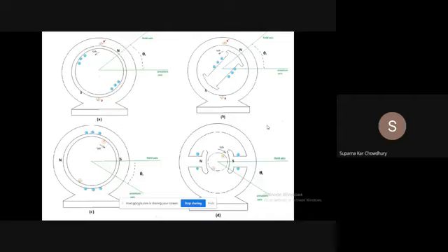So if we put our armature on the rotor, this will automatically put some limitation on the voltage rating of the armature coil. From the current rating point of view, as the current rating increases, the copper content of the winding will increase, because we will have thicker copper sections. That will make the weight of the winding bulky, and so the rotor bulky. That puts a mechanical limitation on the rotor size.